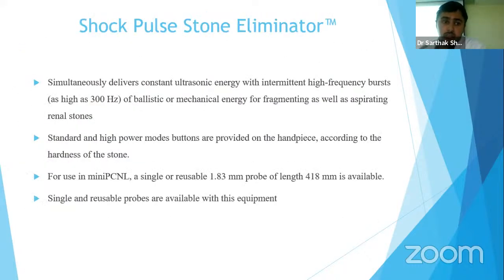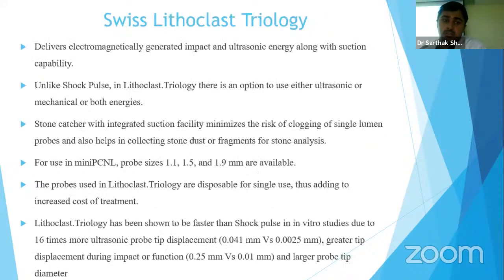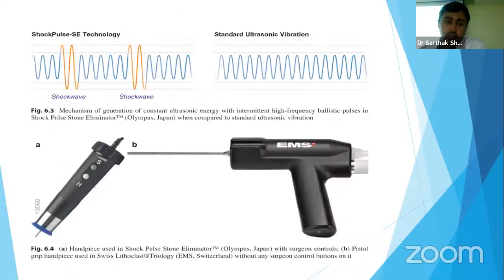Shock pulse stone eliminator utilizes both standard as well as high power mode. The only limitation of this is you cannot use ultrasonic lithotripsy and pneumatic lithotripsy separately, which was overcome by the Swiss LithoClast Trilogy. It gives us an option to use either ultrasonic or mechanical or both energies. It can be used in mini PCNL with probes of 1.1, 1.5 and 1.9 millimeters available.